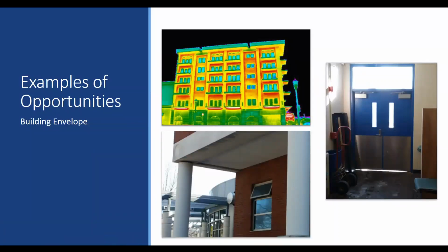In the top left corner, we have a thermal image of an exterior building. Take a moment to see what your building looks like on a cold winter day and on a hot summer day. Doing this can help you recognize insulation issues quickly. In the bottom left photo, there's a window open during the wintertime. So this poses the question, why? Is it too hot in that area and you need the room to be cooled during the winter? How many of us see this in our own buildings? This will require further investigation to get to the root cause, but now you know something more is going on with this zone.